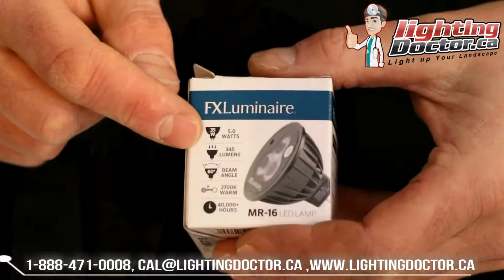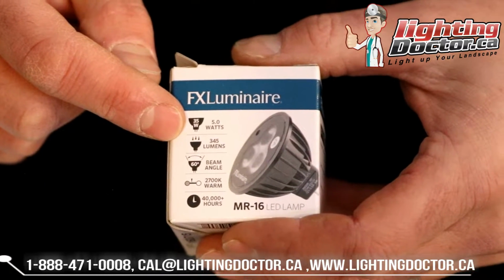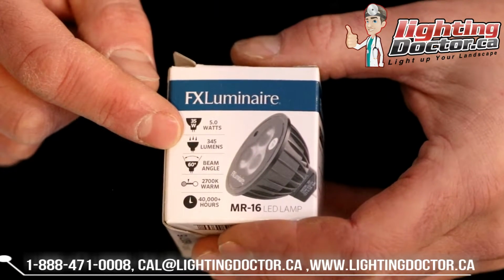If you look on any of the bulbs you're using in your landscape lights, it'll either say on the box what the light is, or if you're switching around bulbs, you'll usually find the information you need on it. But for sizing your transformer, the biggest thing you need to know is how many watts each lamp and each fixture is going to take.